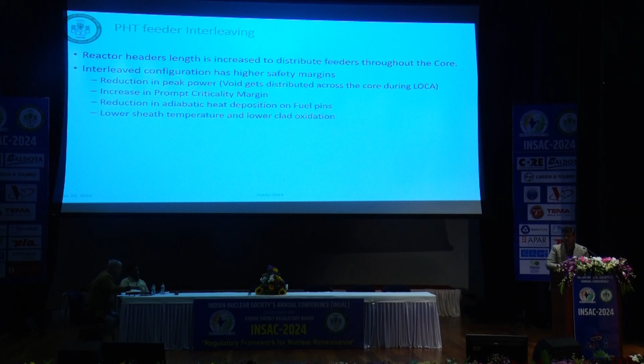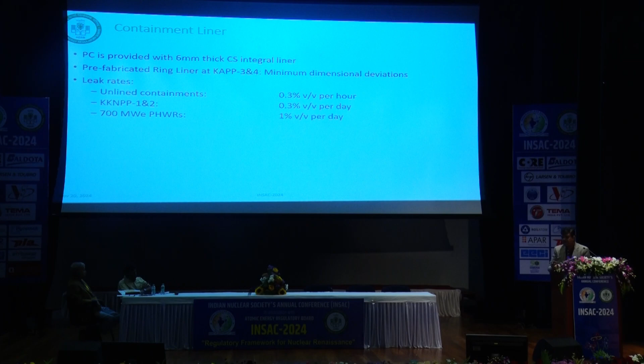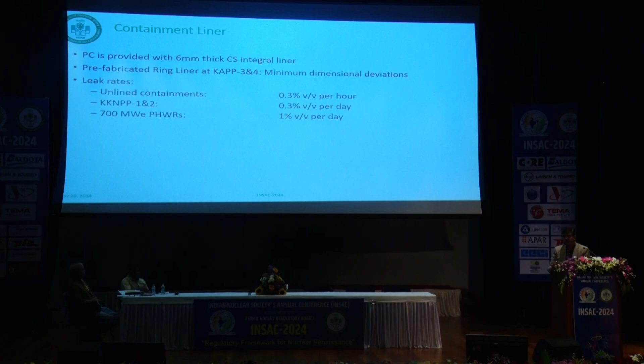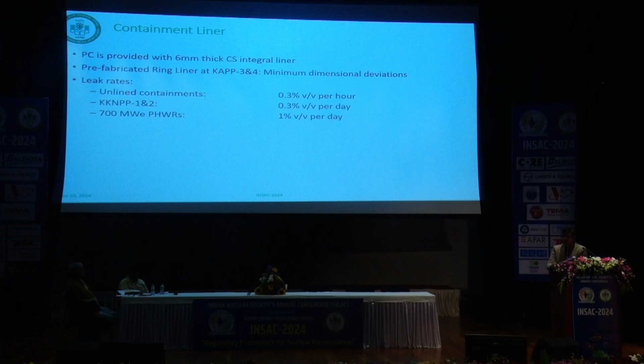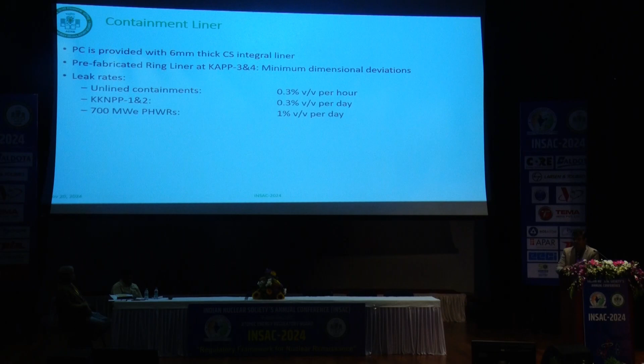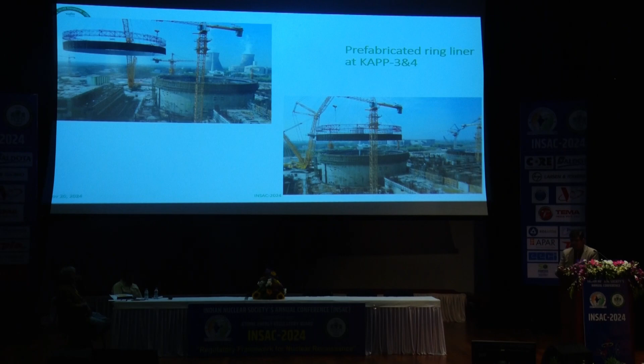Then there is a containment liner. So a 6 mm thick carbon steel liner is there in the containment of 700 megawatt PHWRs, and the leak rates because of which have reduced drastically. If you see the unlined containments of 220 and 540 megawatt PHWRs, the leak rates are around 0.3% per hour. But in case of 700 megawatt PHWRs, the targets are 1% per day. So this is a photograph of the prefabricated ring liner. The ring liner was welded right at the ground, and then it was lifted through the crane and put on the containment. So this practice was adopted in KAPP-3&4, and it gave a lot of benefits during the construction.